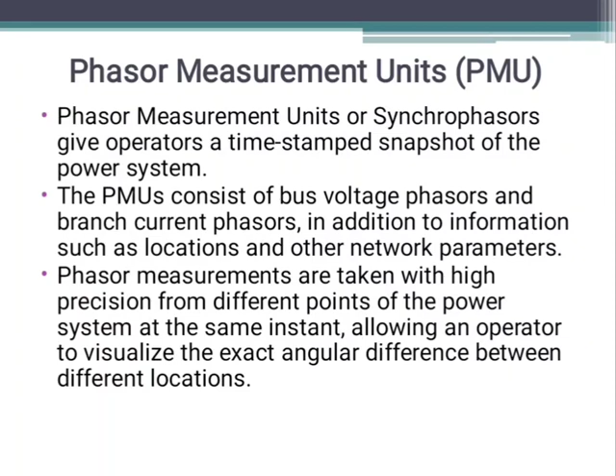These phasor measurements are taken with high precision, with different sensors situated at different points of the power system at the same instant, because that is the best feature of the PMU: at the same instant it will capture the data from different points. That will allow the operator to visualize the exact angular difference between the different locations. From one location to another, how the voltage behavior changes and the phase angle is analyzed when they take the data from different sensors at different locations.